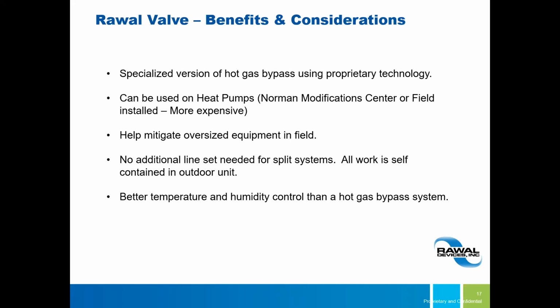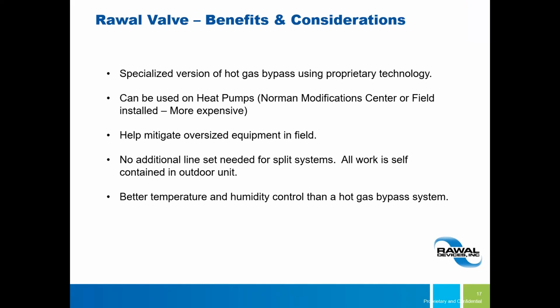So yes, it does help you mitigate issues with oversized equipment if that runs. You don't need another line set for a split system. All of this is self-contained within the unit. You're not trying to add another device on a split system, because it's kind of a different animal by itself. Can you adjust it in the field? I think those valves are adjustable out in the field.